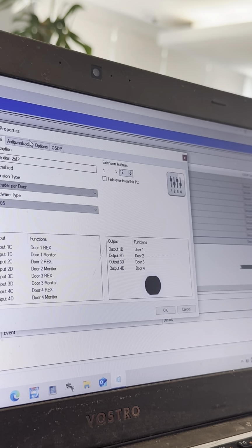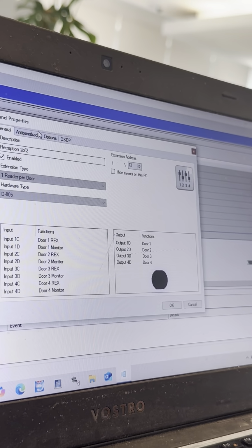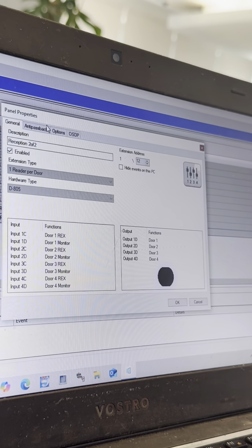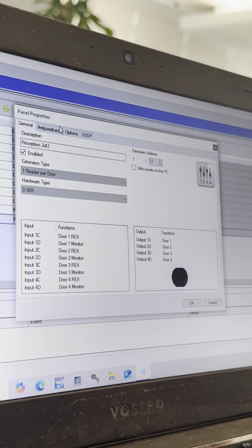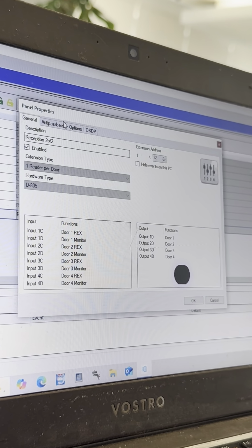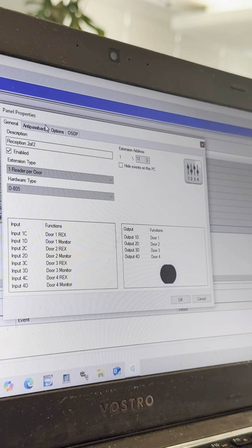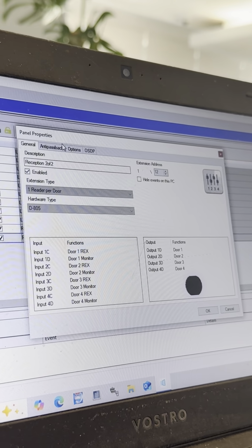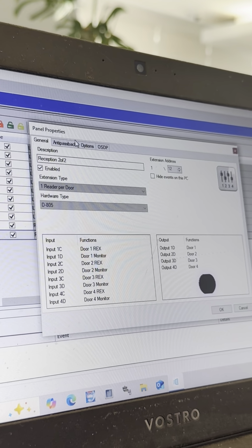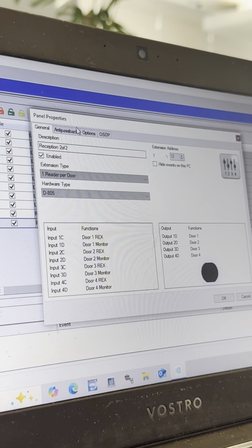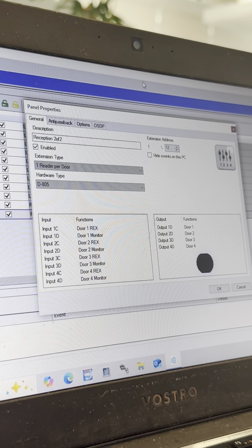Even with the old ones, it's the same. You have to turn it off, change the dip switch, and add it again. But here, you can just delete and add it again, because it's at the beginning. Imagine you did it 2 readers per door, and then they said, no, now we want to have this door for this one and this door for this one, and you've already done it. That programming you added afterwards is not going to work. In fact, it will delete itself.